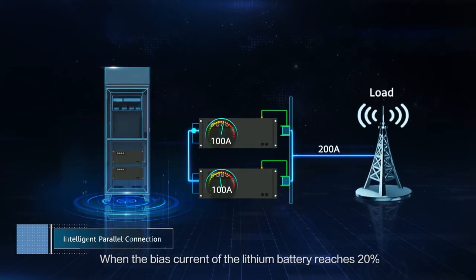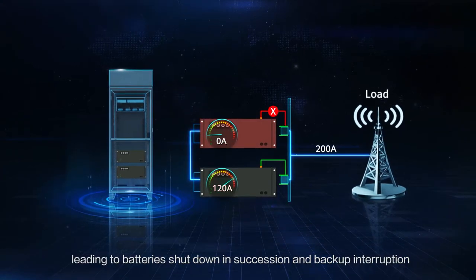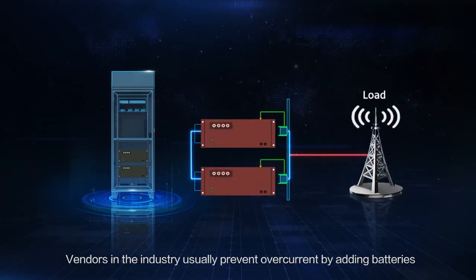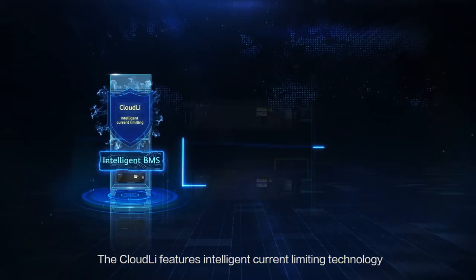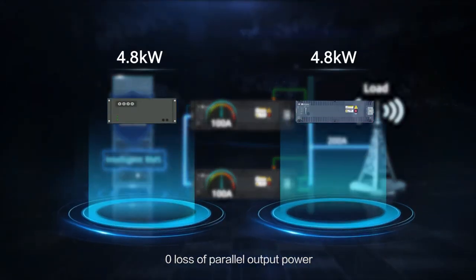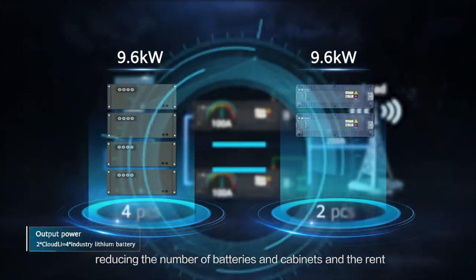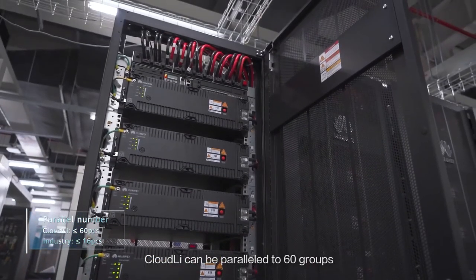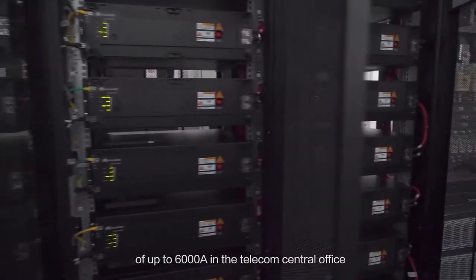There are differences between different lithium batteries. When the bias current of a lithium battery reaches 20%, overcurrent protection is triggered, leading to batteries shutting down in succession and backup interruption. Vendors in the industry usually prevent overcurrent by adding more batteries. The Cloud Li features intelligent current limiting technology — no overcurrent during discharging, zero loss of parallel output power — reducing the number of batteries and cabinets and the rent. Cloud Li can be paralleled to 60 groups, meeting ultra-large load requirements of up to 6,000 amperes in the telecom central office.